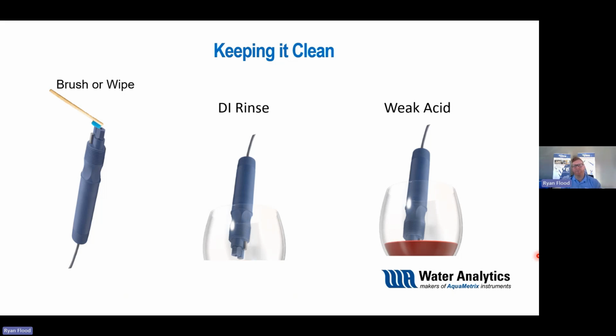And again, if you look back to that previous picture, you can really tell, does it look clean? Is it ready to go? But then it really comes back to as you go through that calibration. If you're struggling to perform calibration and you do the cleaning and then it's back up and running, there's your answer. You've cleaned it well. Sometimes it's worth giving that little extra, with a soft bristle brush or a nice clean wipe, and you give it a little bit more. Again, be careful of the glass, and you're back up, ready to go.